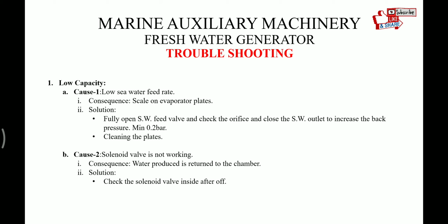Second is solenoid valve is not working. Consequence: water produced is returned back to the chamber. So in this case, check the solenoid valve, and check if it is leaking or if it's not working at all.